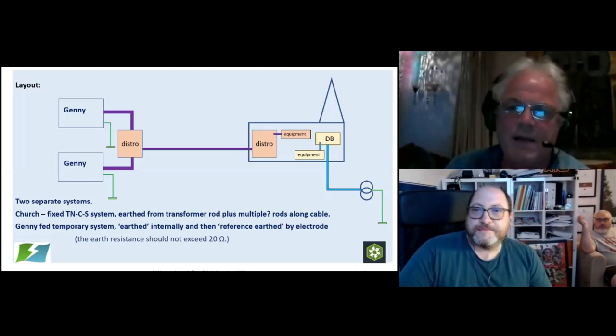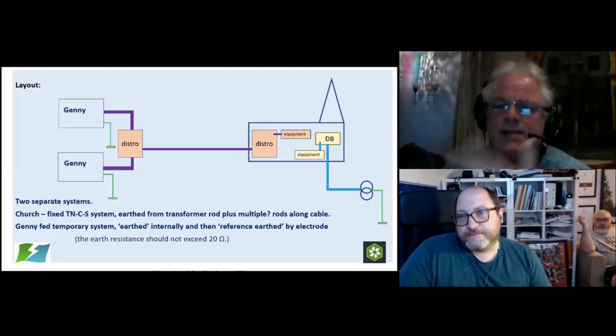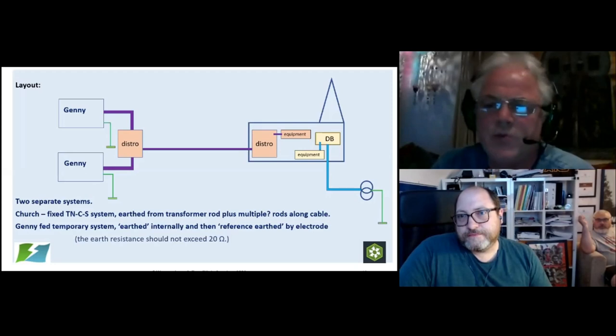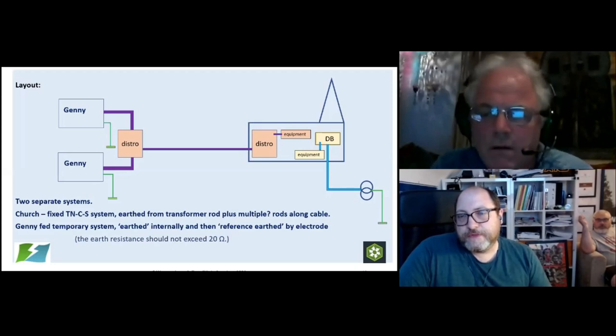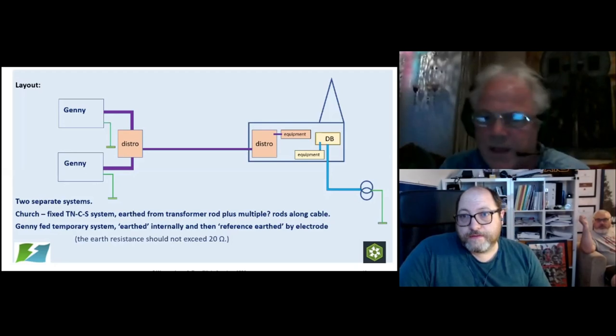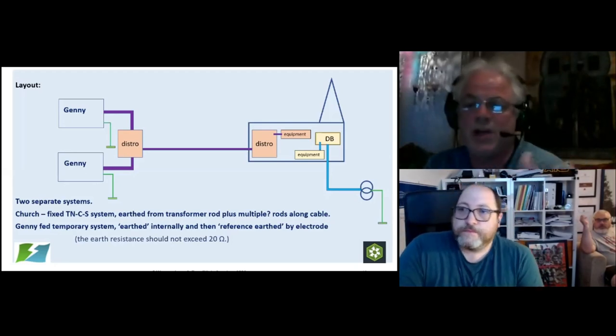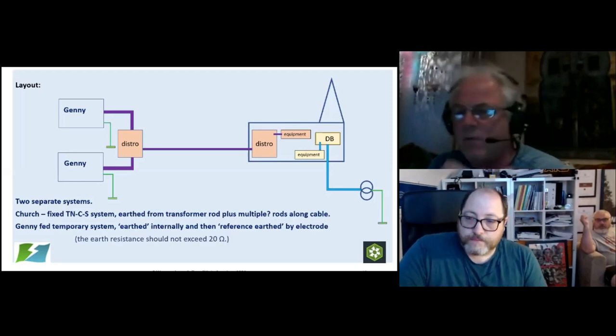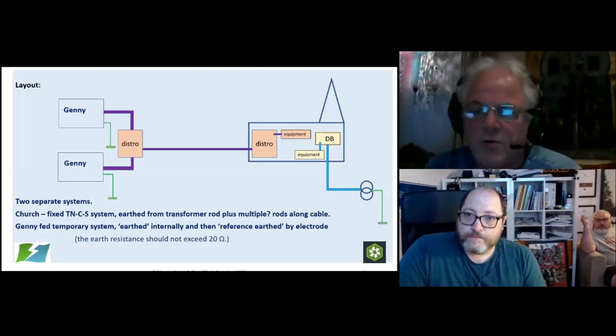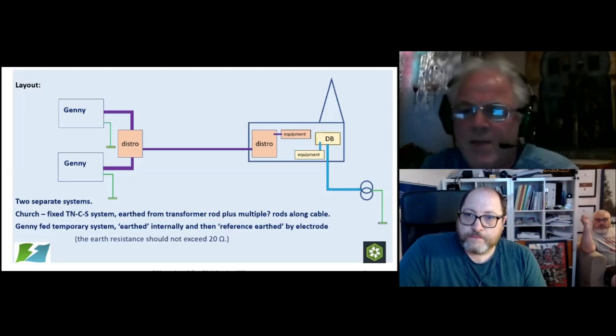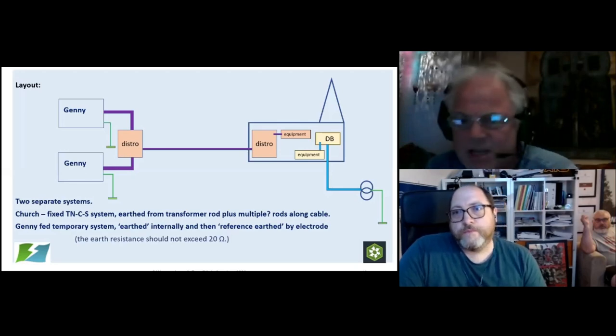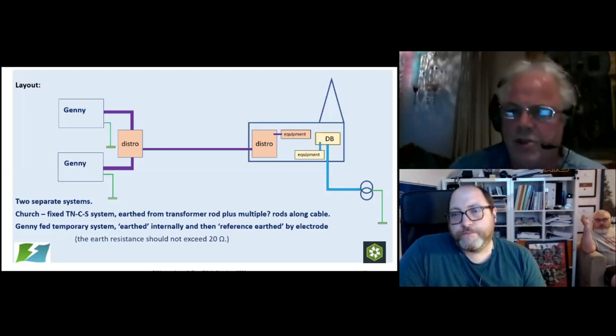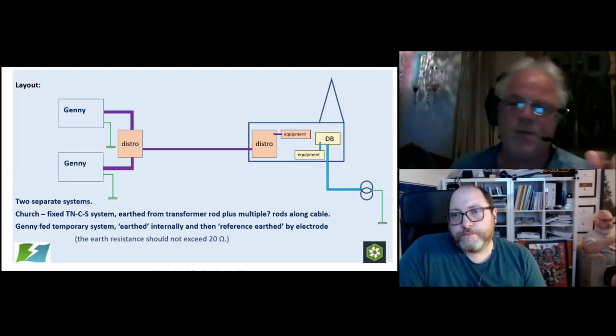And if you read 7430, it does say that main earth terminals are very rarely at zero, because of all sorts of things, fault currents and leakage and this, that, and the other. They're very rarely at zero, which is why we could get a difference in potential between the two earth systems. If your fixed installation in your church, if the MET there is not at zero, maybe at several volts, and your generator system is at several volts, it might be in the other direction.